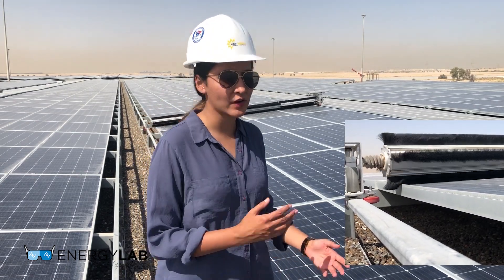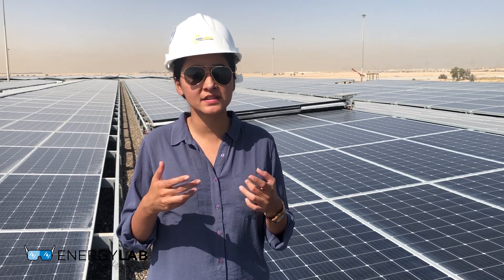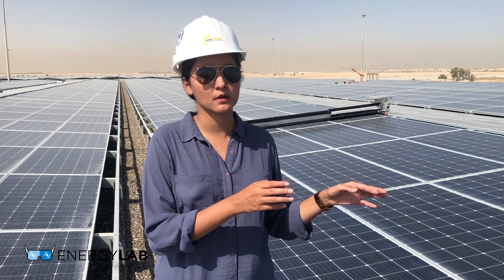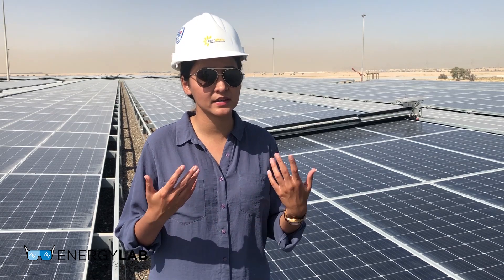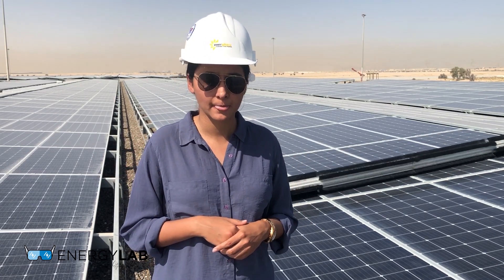As you can see, these are the rails that the robot runs on. One of the issues we face is the robot getting stuck, but as soon as that happens we can monitor it online and receive an alert on the monitoring platform, then instantly send somebody on site to resolve the problem. How frequently do the robots get stuck? It depends on the commissioning phase. In the initial stages it happens fairly frequently as we fine-tune the rails and the robotic system, but once the project is fully commissioned and tested, we face such issues probably once a week.